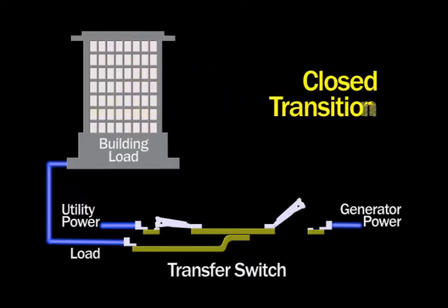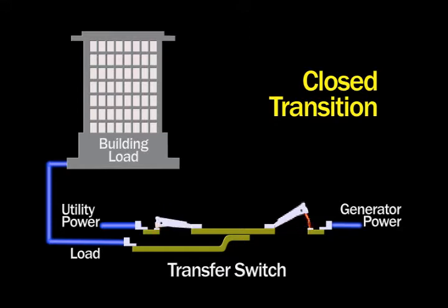Closed transition mode utilizes make before break switching, which allows the power transition to be completed with no loss of power. The two power sources must be synchronized at the time of transfer.